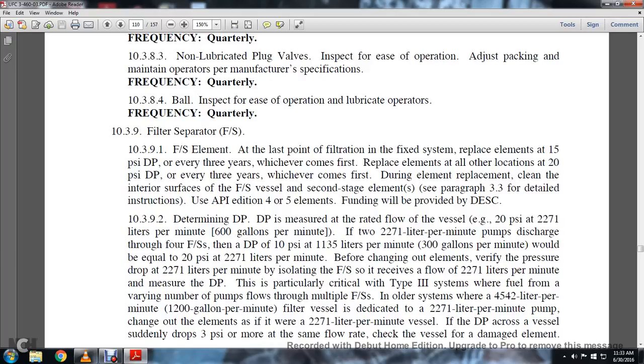10.3.9 Filter separator. The filter separator element at the last point of filtration is fixed. Replace the element at 15 psi DP or every 3 years, whichever comes first. Replace the element at a location of 20 psi DP or every 3 years, whichever comes first. During the element replacement, clean the interior surface of the filter separator vessel. Second stage element: see paragraph 3.3 for details and instructions. Use API edition 4 or 5 elements. Funding will be provided by DESC.